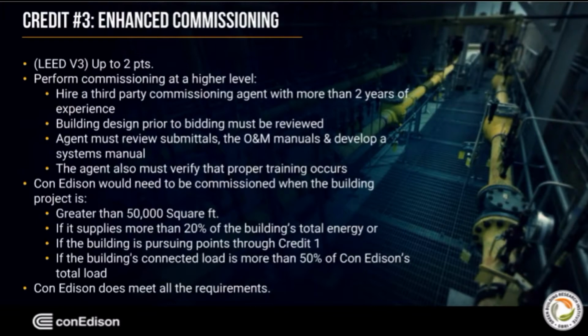The district energy system itself must also meet the guidelines if the project building is greater than 50,000 square feet, or if the DES supplies more than 20% of the building's total energy, or if the building is pursuing points through Credit 1, or if the building's connected load is more than 50% of the DES total load. One of these will most probably happen, so the DES will need to comply as well. In this case, and the case of Con Edison, the company complies with all of these.